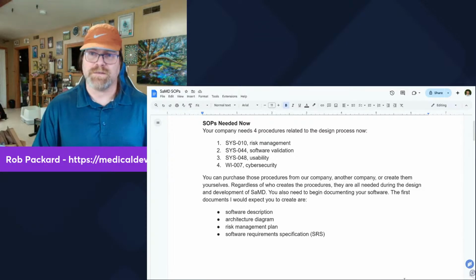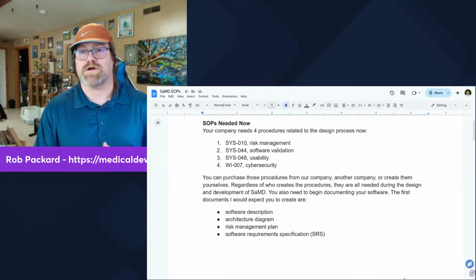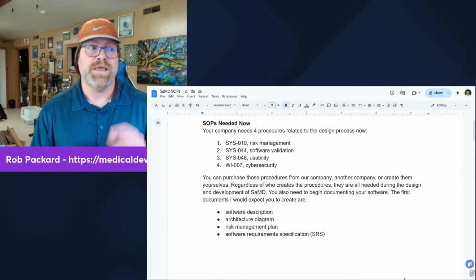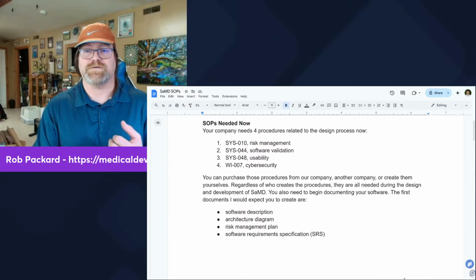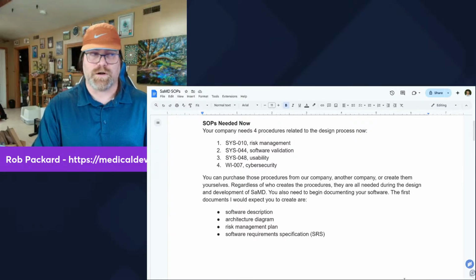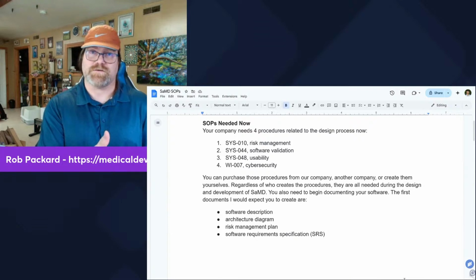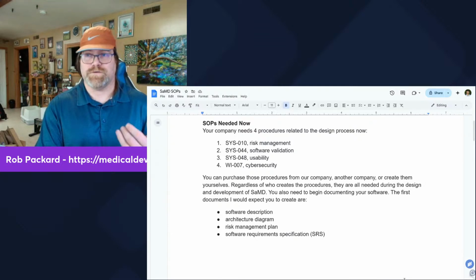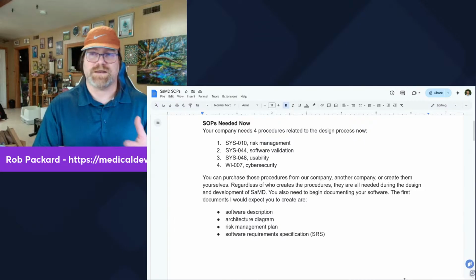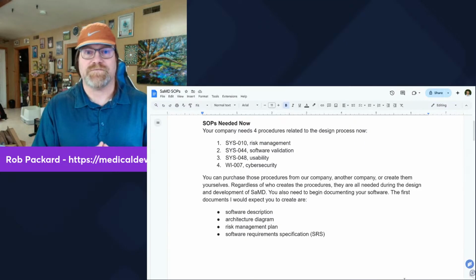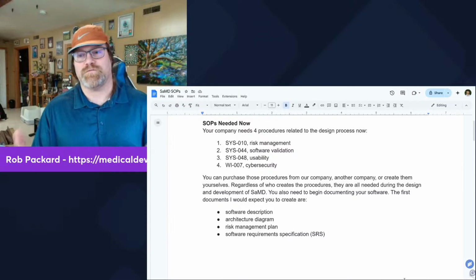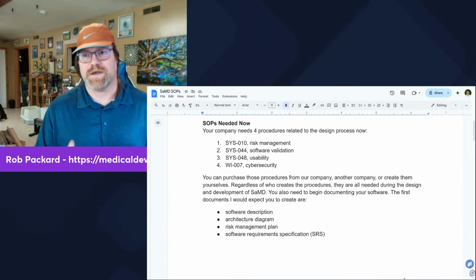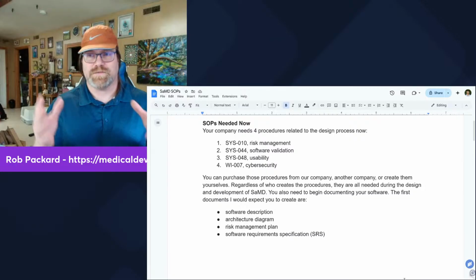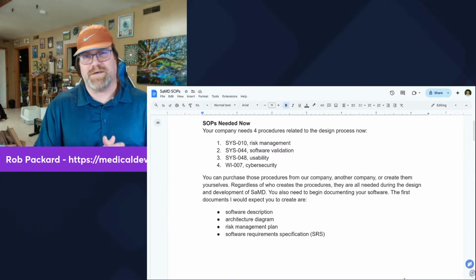Next, you have a risk management plan. The risk management plan is now required in the FDA eSTAR as well. It used to just be a hazard analysis for software. Now they want the risk management file, the whole file, including at a minimum the plan, the hazard analysis, and the risk management report. But your plan should identify what activities there are going to be. So your hazard identification would be your next thing after your plan. The next thing after that would be identifying risk controls for your software, and then would be iterative testing to verify the effectiveness of the risk controls and the completeness. You do a benefit risk analysis, and you do a final risk management report when you're all done. And now you have the elements. Even though the FDA says we only want at minimum these three things, you should really have a lot more.